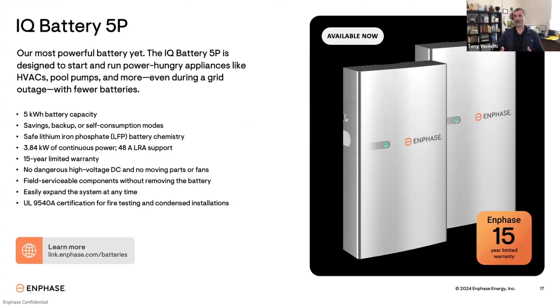We use the safest battery chemistry available today, which is lithium iron phosphate. It's much less susceptible to thermal runaway, and we have the UL 9540A battery safety certification to prove that. The power output is here at 3.84 kilowatts. I want to remind you that that is for a single unit, and most systems are going to have 2 or 3 or 4 of these units to achieve the right storage capacity for that homeowner. Because it's an AC coupled system, every time you add another battery, that adds on to the power output as well as the energy capacity. So I'll go through some examples here in a minute.